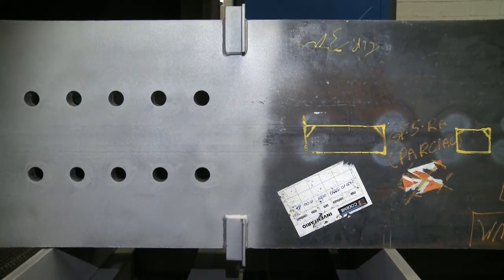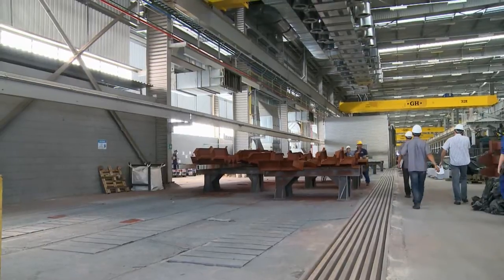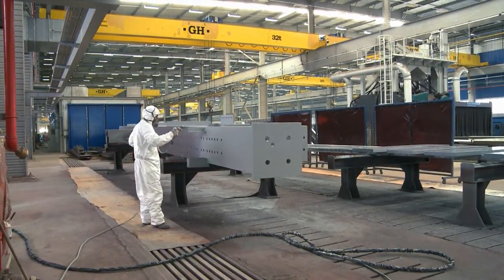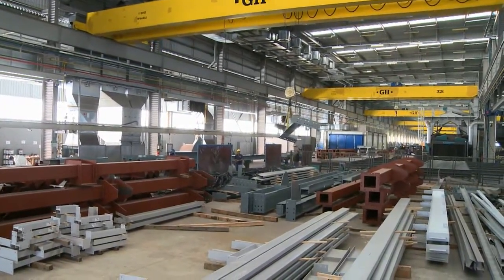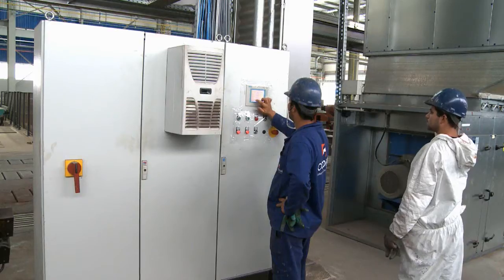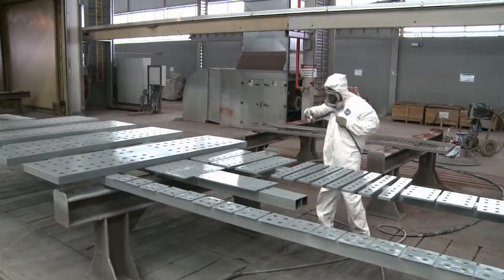The quality of the blasting result makes it possible to give workpieces a high-quality coating. The next stop in the SLF processing line is the open space coating area. In order to accommodate the high volume of workpieces, the 54-metre-long area was divided into three coating stations, each measuring 18 metres. Above the entire coating area, 36 long-range nozzles were installed in two rows under the building ceiling. The specially developed nozzles are able to feed fresh air from a great height to the active work section. This fresh air is filtered to remove dust and can be warmed to a temperature 2 to 3 degrees above the building temperature. Three extraction ducts are located in the floor area of the coating section to capture and extract the targeted airstream below.